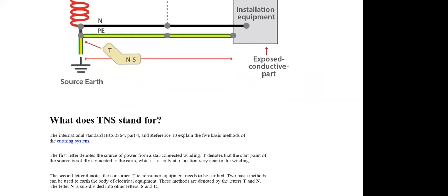As you see, the first letter denotes the source of power from a star connected winding. T denotes that the star point of the source is solidly connected to the earth, which is usually at a location very near to the winding. This is what we are trying to say. This is T, this is NS, and this is the source. This is the source, and NS is the other part, the installation equipment, which needs to be connected.